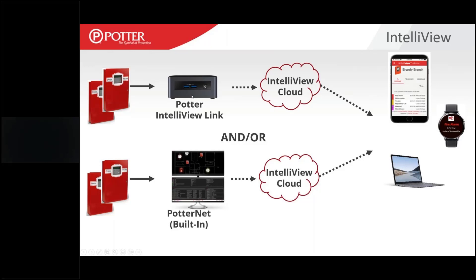It doesn't matter as long as you can make connectivity to the panels. You provide the IP address and user code — that's really all you need to do. It will make those connections to the panels and then make the connection to IntelliView. You do need to get yourself an IntelliView account. It literally takes minutes — go to potterintelliview.com, create a username and password, and use that when you set up your IntelliView link. It will start sending events into your IntelliView account.